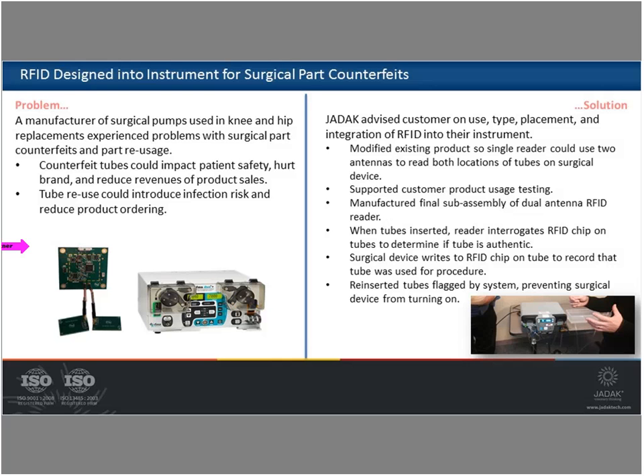So when a new tubing set is inserted into the instrument, the reader writes to the tag, ensuring that the tubing can't be used again once it's disconnected. And to ensure that third parties couldn't simply copy the RFID tags and offer replacement hoses, the tags are password protected. As I say, the HF tags are very good with security.